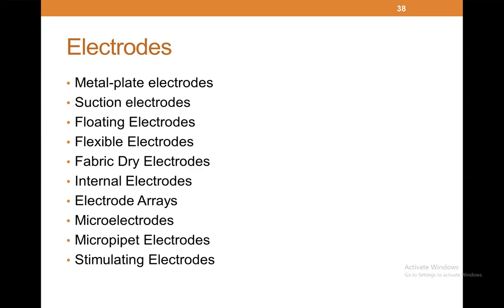Okay. So what you just said, one of the advantages is that it has high conductivity, and you can reuse it, but then it has high skin impedance. You actually need to add a conductive paste to maintain contact with the skin. It also degrades. Another application is that it's used to stimulate signals, so it's used as a paddle in defibrillators. You might see in TV shows the paddle electrodes going into the heart, open heart, and they deliver current, versus the external defibrillators that we talked about.